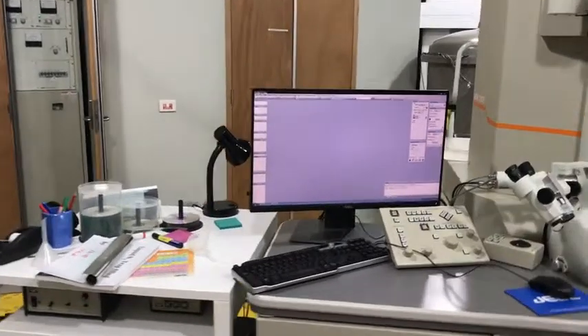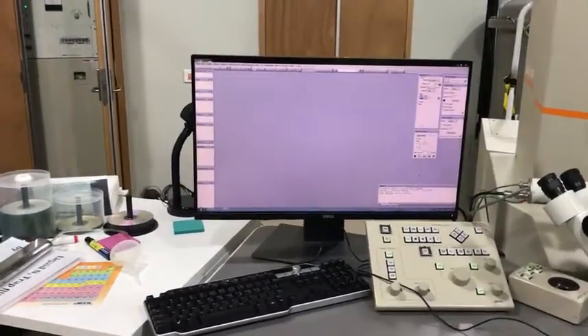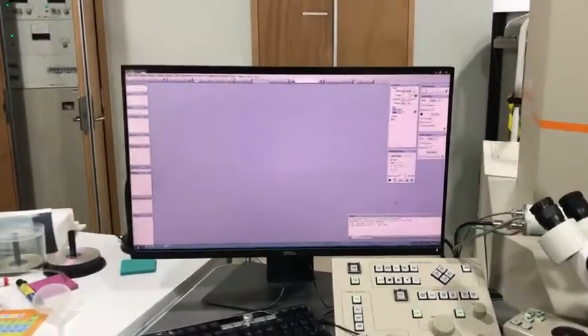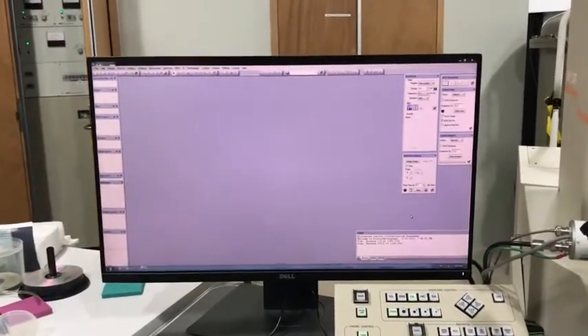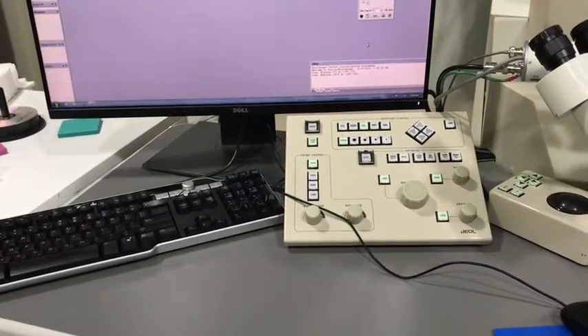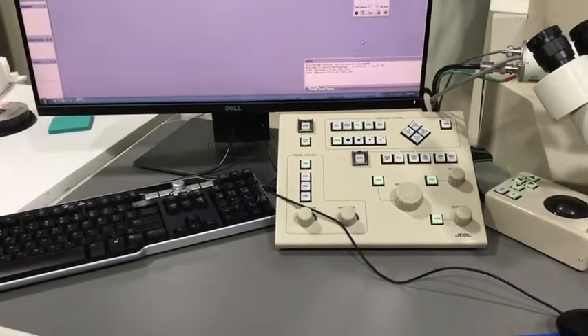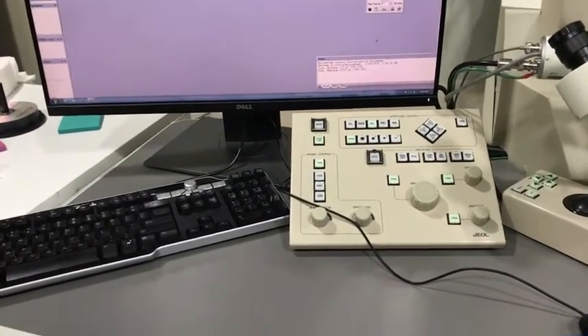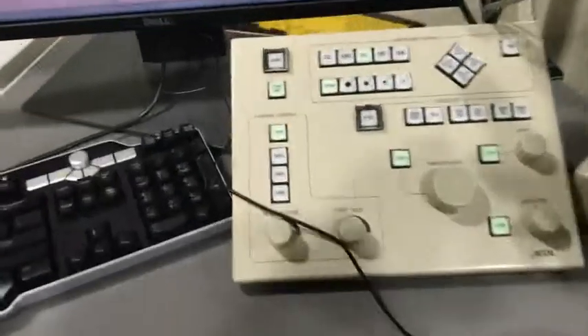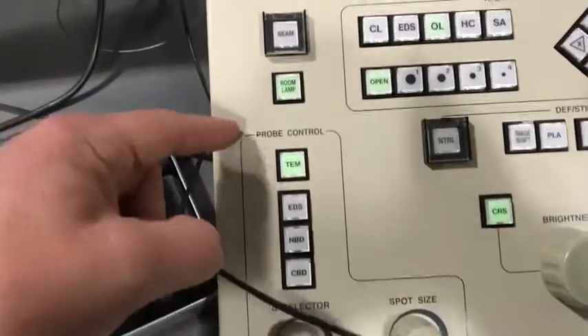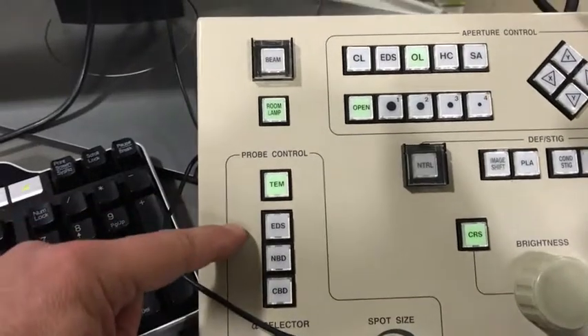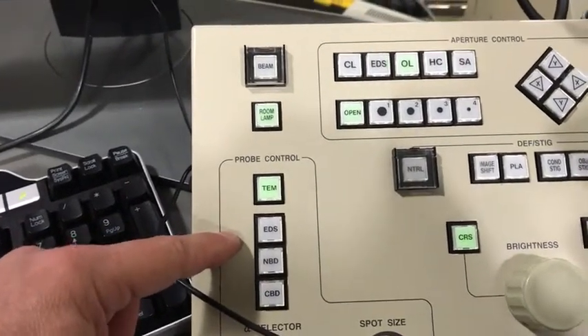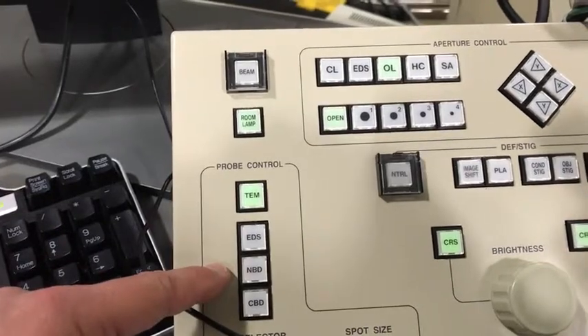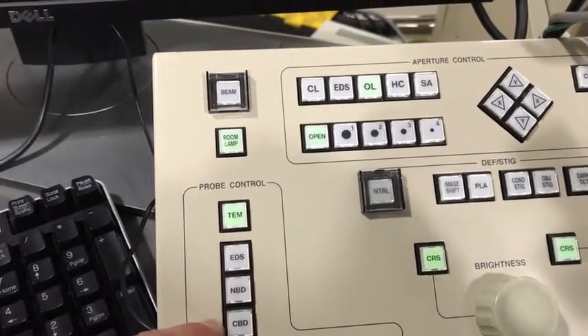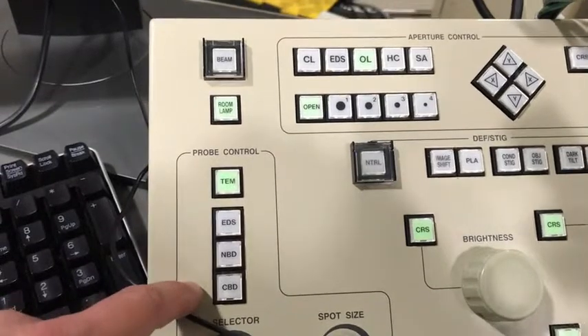Okay, I thought I'd give a bit more detail about some of the instrumentation and control. So that's the Gatan computer, and that's where we're going to be doing all of our imaging, because we don't use film anymore. That's the left-hand control panel for the microscope alignments and probe positioning and imaging conditions. And notice that we've got several modes that we can operate in. We'll be operating in TEM mode. You can also use specialized EDS alignments, nano beam diffraction alignments, and CBED alignments. I very often use CBED because I'm a CBED specialist.